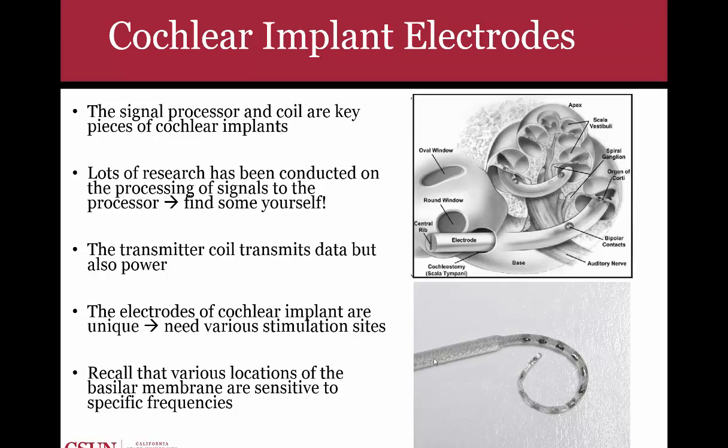Notice how a lot of these electrodes, they have little wires or leads. They are kind of zigzaggy. That's to accommodate for the bending that is necessary for this electrode to sit inside the cochlea. So there's a couple of things you have to keep into consideration. The other thing too is the material here.